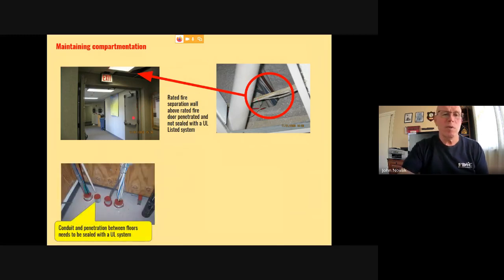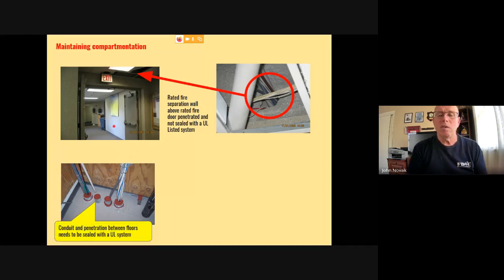So that becomes important when we talk about penetrations and separations, especially in fire-resistant buildings. Down here we have a floor being penetrated by IT cable and electrical cable and conduit. But everything in here is sealed with what they would call a UL listed system. Right. So if you go to the UL website, the UL catalogs, you can look at what type of floor system you're going to penetrate, what kind of material is going to penetrate the floor system, and they give the contractor UL diagrams of how these penetrations are supposed to be sealed up.